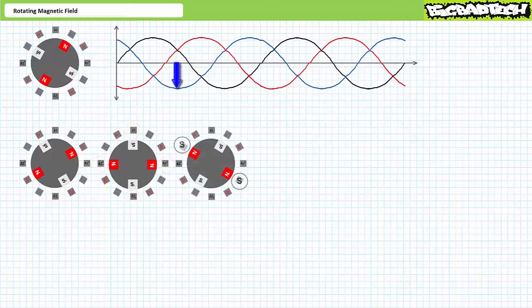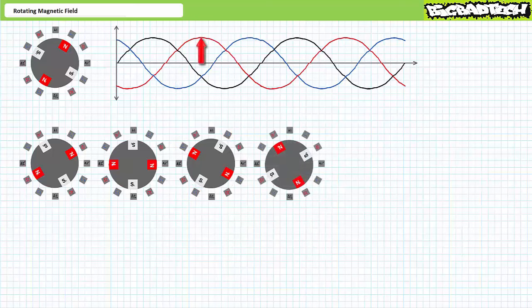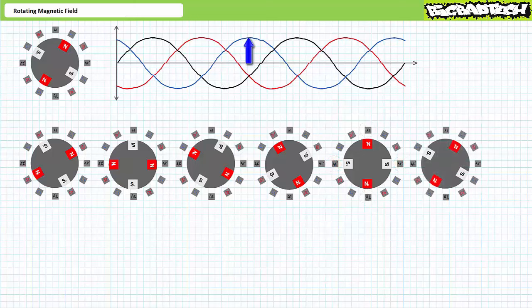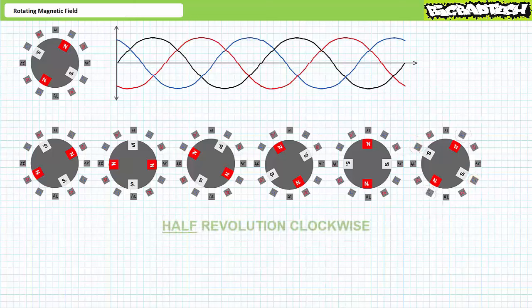When L3 peaks negatively, C ends are south and prime ends are north — clockwise continues. When L2 peaks positively, B ends are north and prime ends are south — clockwise continues. When L1 peaks negatively, A ends are south and prime ends are north — clockwise continues. When L3 peaks positively, C ends are north and prime ends are south — clockwise continues. After one full cycle of three-phase AC, we've completed only half a full rotation — 180 degrees. The next full cycle brings the rotor the remaining 180 degrees.